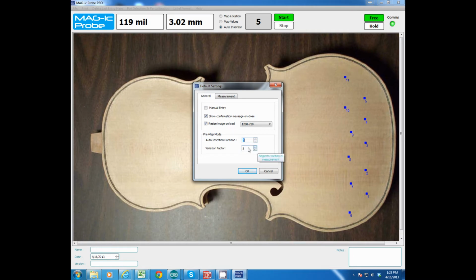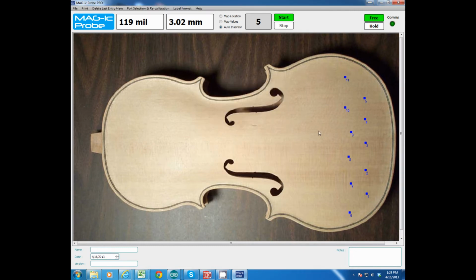If you want to increase or decrease the stability factor, you can. Once I start, it'll start this counter if my probe value is stable. You'll see the counter will go down to 3, and then that value will be entered in location number 1 as soon as it's stable. If I make the probe unstable, as if I'm moving it around, the counter will go back to 5 until it's stable.